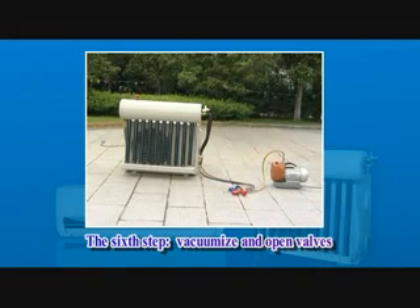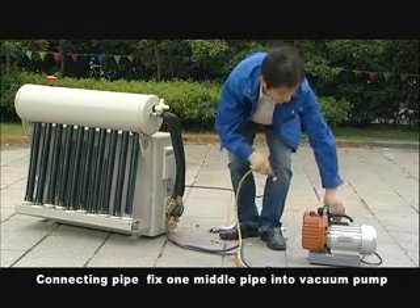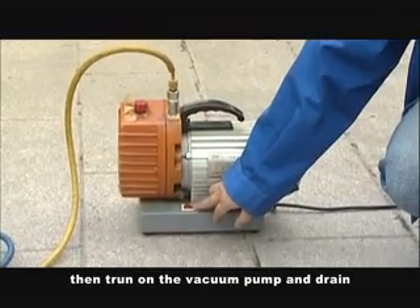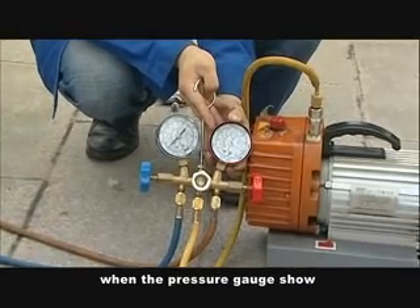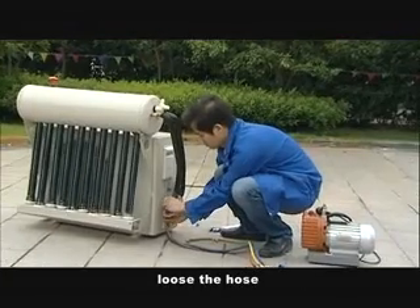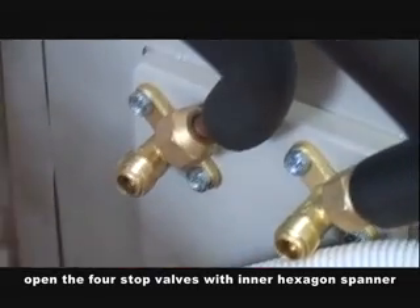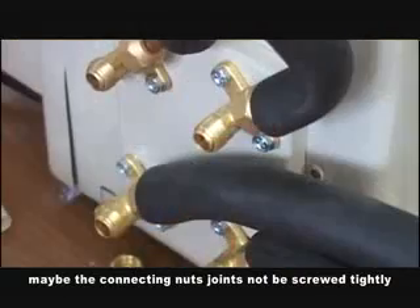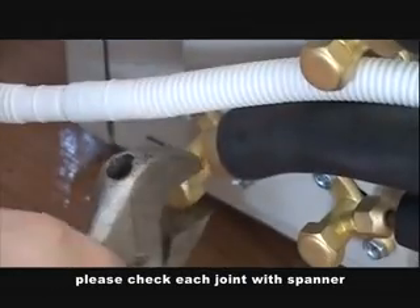Sixth step: vacuumize and open valves. Connect the two stop valves with the pressure gauge and connecting pipe. Fix the middle pipe into the vacuum pump. Then turn on the vacuum pump and drain out the air from the indoor unit and water tank. When the pressure gauge reads below minus 20, you can turn off the vacuum pump. Loosen the hose and open the first stop valve with the inner hexagon spanner, then screw all nuts tightly. If it cannot reach minus 20, the connecting nuts may not be screwed tightly — please check each joint with a spanner.